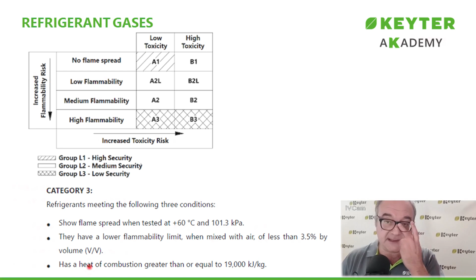Category 3, of course, is going to be just the opposite. It's going to do things that Category 2 is not capable of doing. Here they show propagation as before, when tested at 60 degrees Celsius and 1 atmosphere. It has a lower flammability limit below 3.5%, that is, low concentrations capable of combustion, and its heat of combustion is greater than 19,000 kilojoules per kilogram.